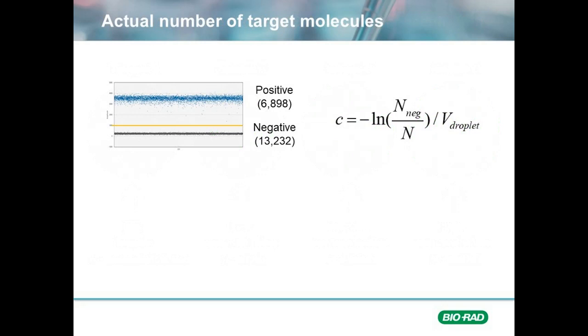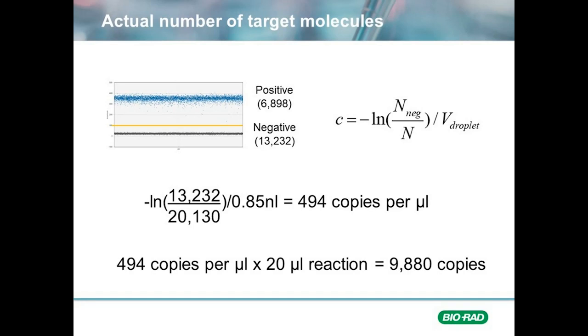Let's go back to our first example where we saw 6,898 positive droplets and 13,232 negative droplets. We can calculate the actual concentration by using Poisson's equation. The negative ln of negative droplets, 13,232 divided by the total number of droplets read, 20,130, and then divided by the volume of our droplets, which in this example is 0.85 nanoliters, would give us a concentration of 494 copies per microliter. We would multiply this value by the number of microliters in our reaction, in our case 20, and get a total value of 9,880 copies for the entire reaction.